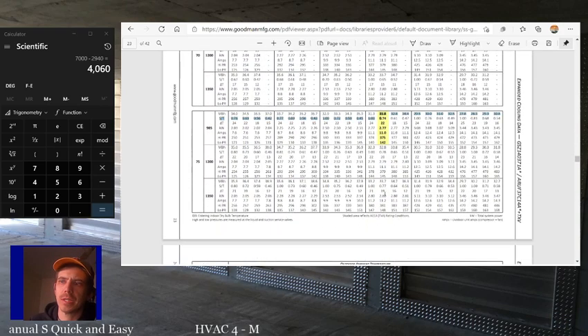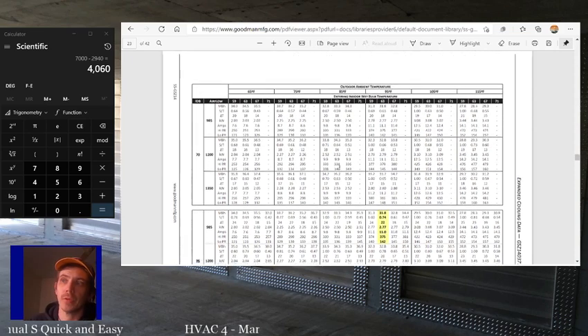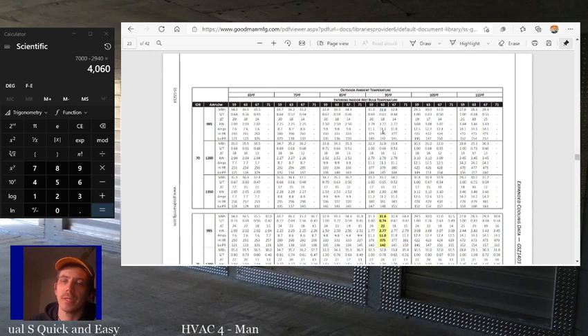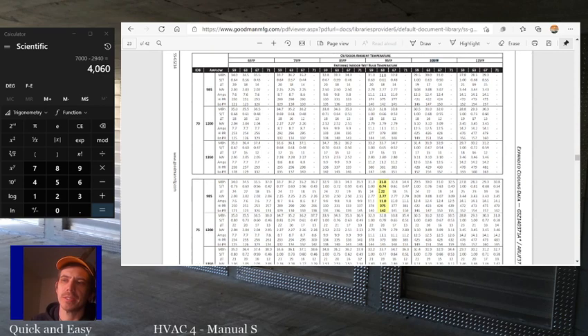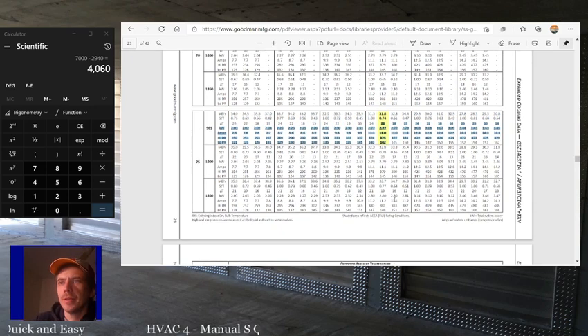If we look at this one, it says the shaded area reflects ACCA conditions. So at 75 degrees inside, we're always 75 degrees inside for cooling, right? 63 degrees wet bulb, that's 50% humidity. So at 50% humidity, 75 degrees inside, and then it says 95 degrees outside. Now the 95 degrees actually depends on where you live. You might design for 85 degrees outside where you live. You might design for 105 degrees outside where you live. But in general, a lot of places are going to be at 95 degrees. So I guess that's why they picked that shaded area.